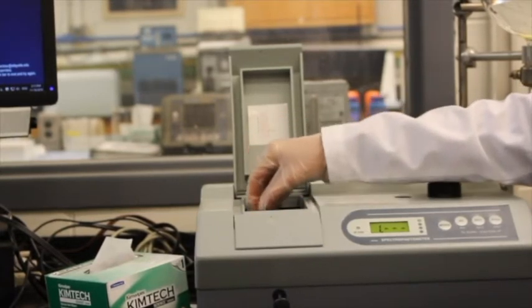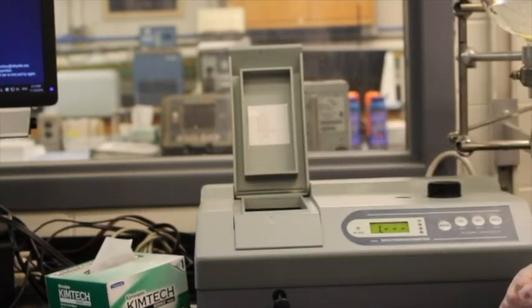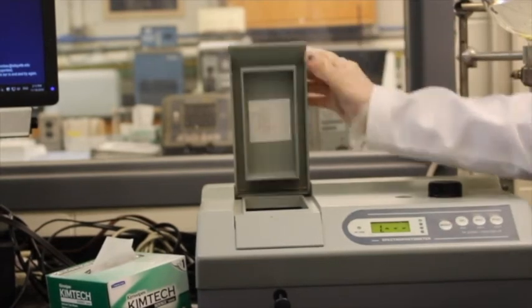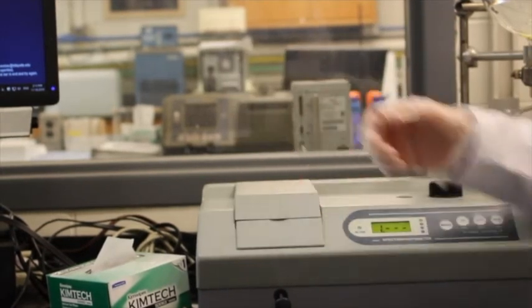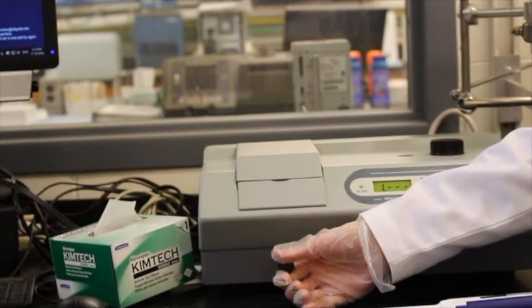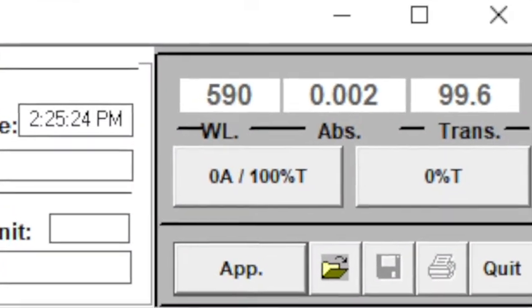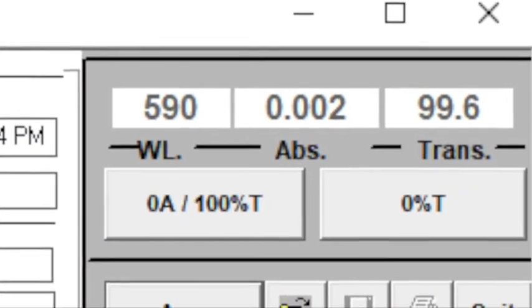Insert the filled cuvettes. Do not test multiple samples in the spec simultaneously. The same slot that was used to blank the system should be used. Ensure the dial is still in the correct position to read the desired slot. Record the absorbance displayed on the screen for each trial.